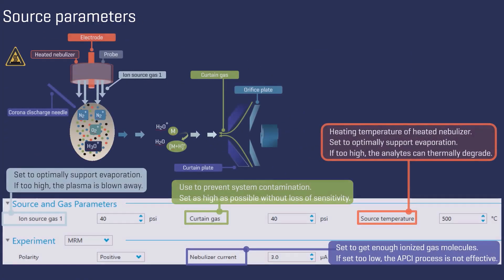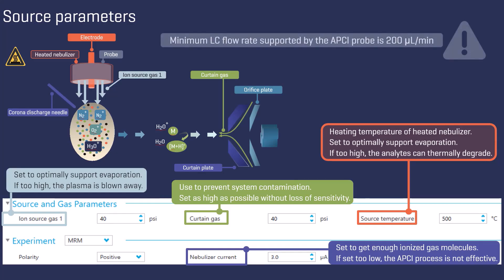It is essential to optimize the source parameters when using atmospheric pressure chemical ionization. Note that the minimum flow rate supported by the APCI probe is 200 microlitres per minute.